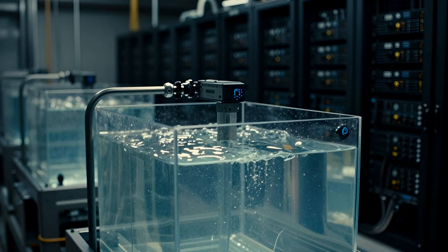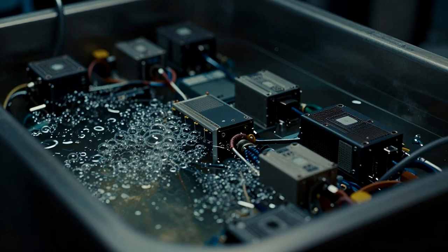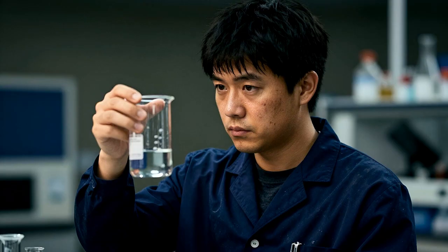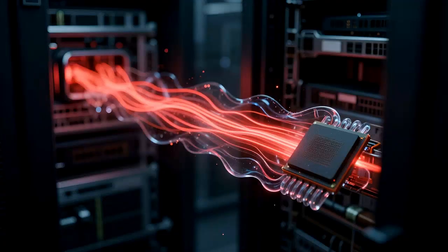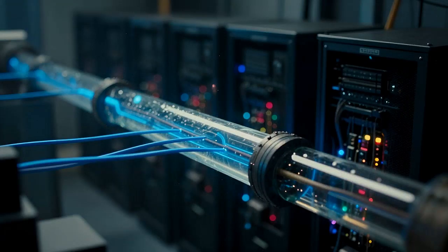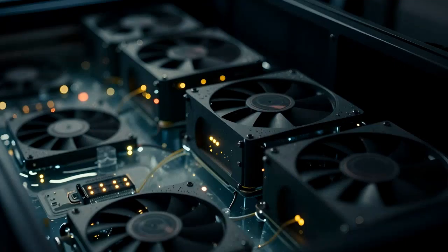Watching an active immersion cooling tank in operation is a visually jarring, highly counterintuitive experience. Millions of dollars of active, fully powered electronic hardware sit completely submerged in what appears to be a bathtub of water. However, the fluid is definitively not water. It is a highly engineered, synthetic dielectric fluid. Dielectric fluids possess excellent thermal conductivity, allowing them to move heat, but they possess near-zero electrical conductivity. Because they do not conduct electricity, the live servers do not short-circuit, even when fully bathed in the liquid.